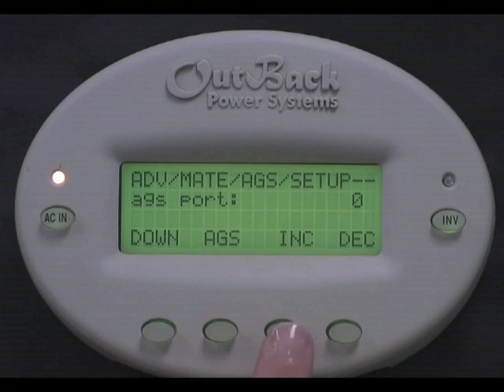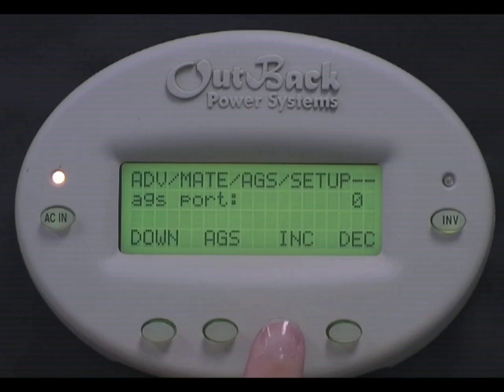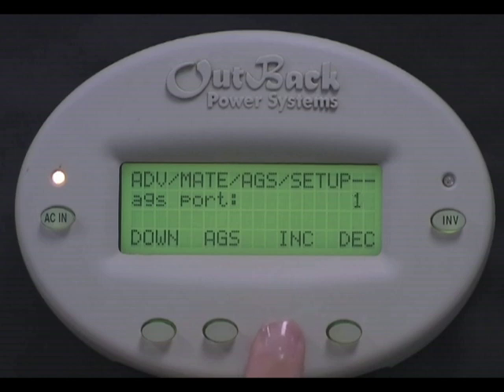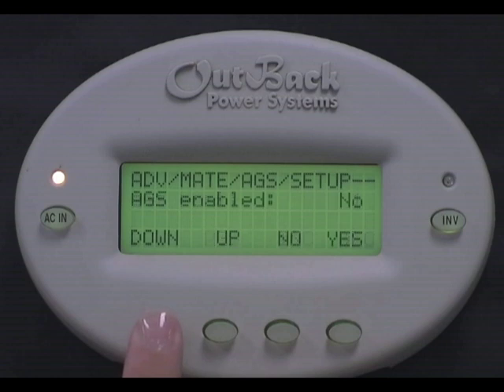AGS port number should coincide with the port number on the hub that you have the inverter plugged into. For instance, if you are using your master inverter's auxiliary port to control AGS, this number would be 1 because your master inverter should be in port 1 of the hub. If you do not have a hub in the system and your Mate is plugged directly into the inverter, this number should be 0. Press down.